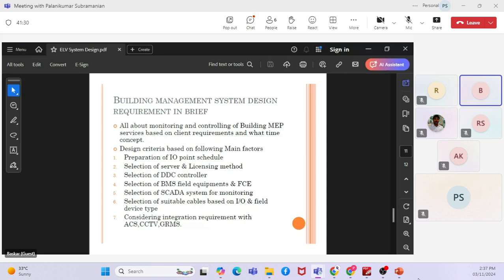Choosing the cables also matters because it will increase or decrease the cost by a huge amount. As you all know, the building management system is connecting all the field equipment and the final control equipment. It's like plenty of equipment connecting to the DDC. It's an individual wired system. Mostly it's a hardware system, individually wired. So cables come in very long distances. So choosing the cable, the thickness of the cable, screened or unscreened cable, or cable with higher thickness or the standard required thickness, is also vital in selecting the BMS system.